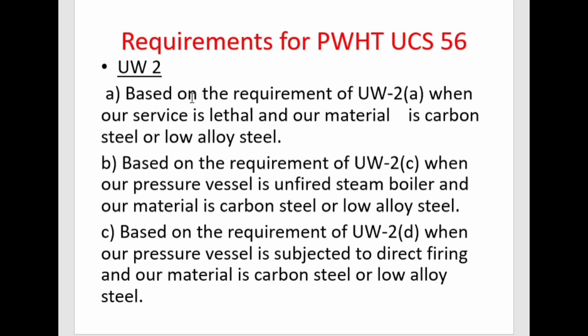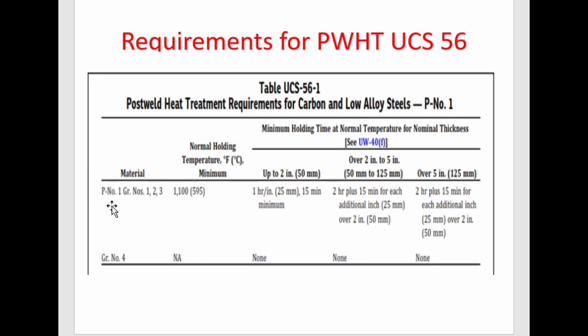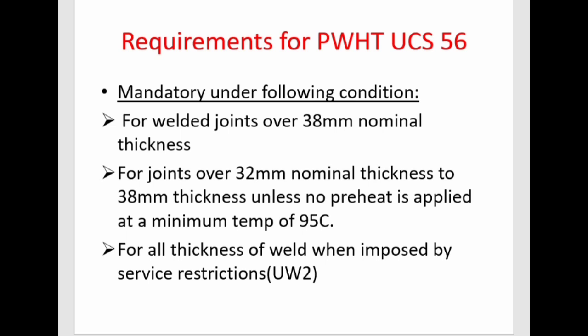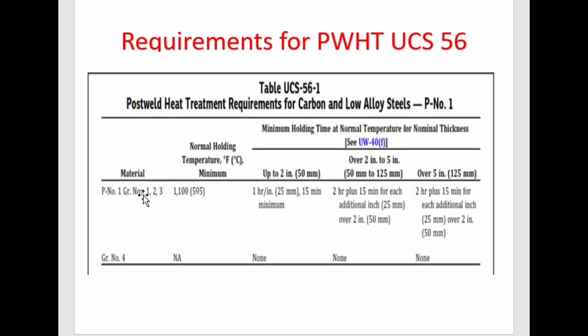Looking at UW-2: UW-2A states that when the service is lethal and the material is carbon steel or low alloy steel, PWHT is required for all thicknesses of material. No matter whether the thickness is 38 mm, 20 mm, or 15 mm — PWHT is mandatory for lethal services for P-Number 1, Group Numbers 1, 2, and 3 materials.